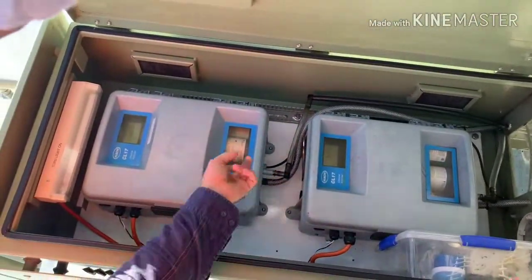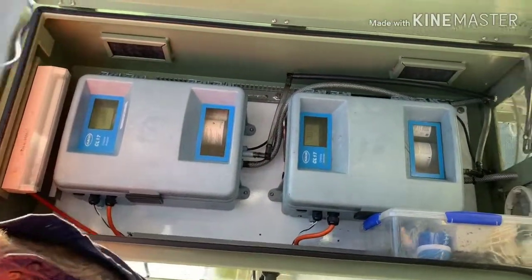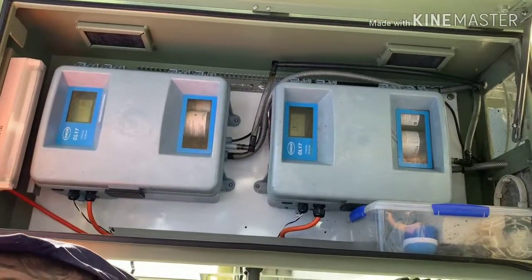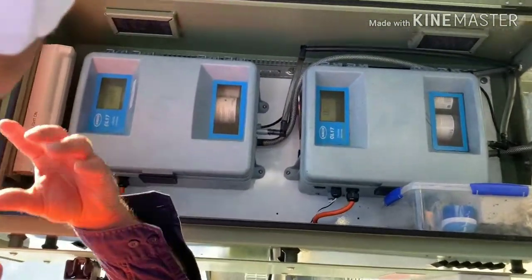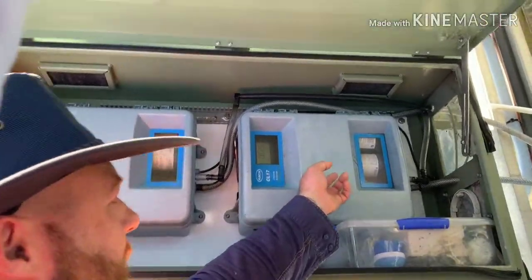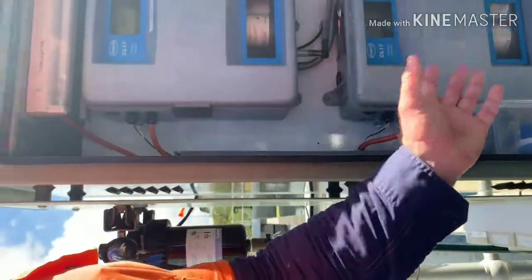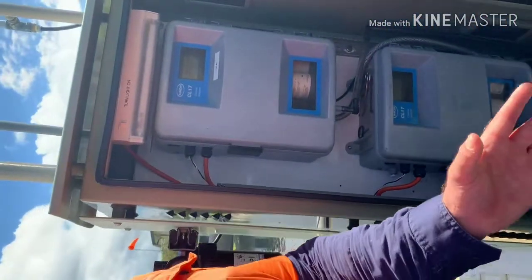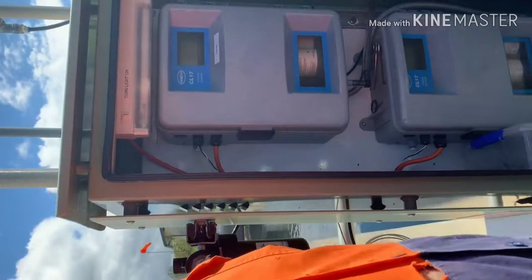So take it out of the contact tank, and we've got reagents in here, so it'll go up into here, and it'll basically do a chlorine test every 45 seconds, tell us how much total chlorine we have. And down the bottom, this tells you how much total chlorine is in the effluent after it's been dosed with SBS, sodium bisulfite solution.